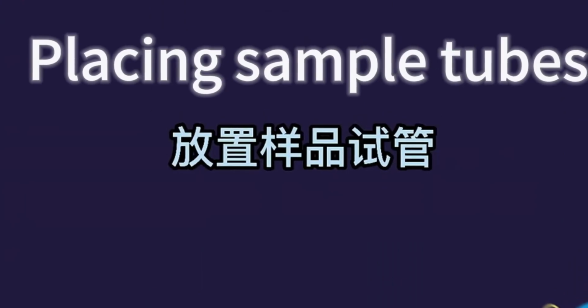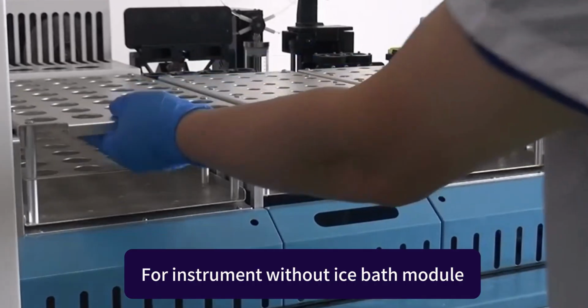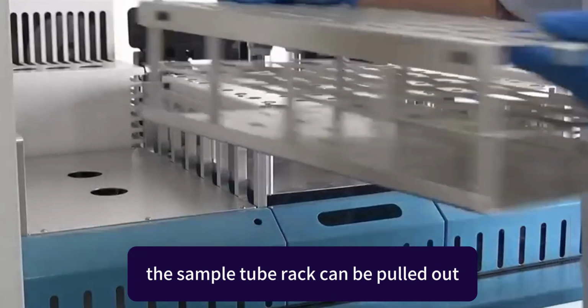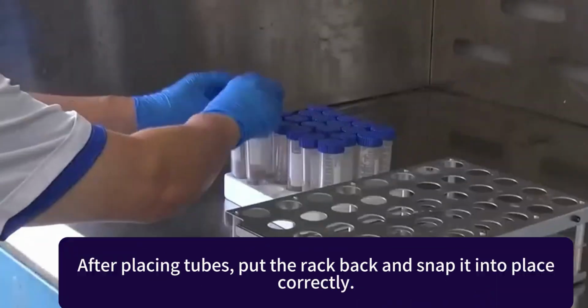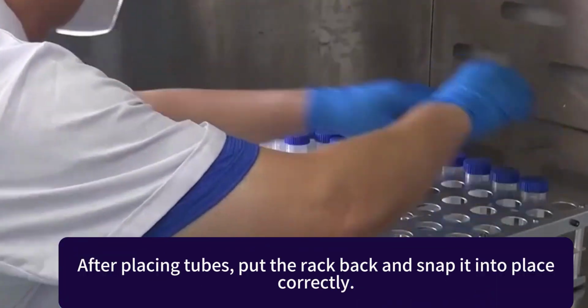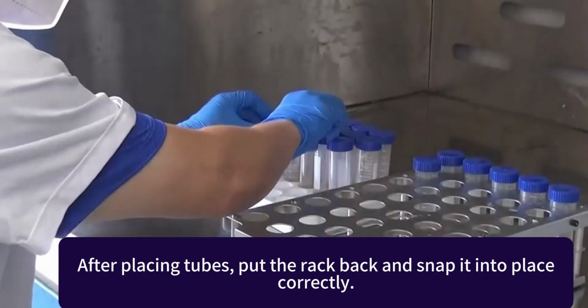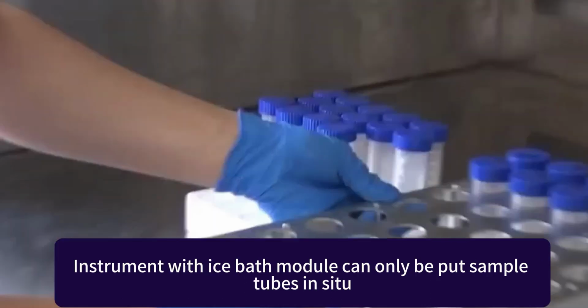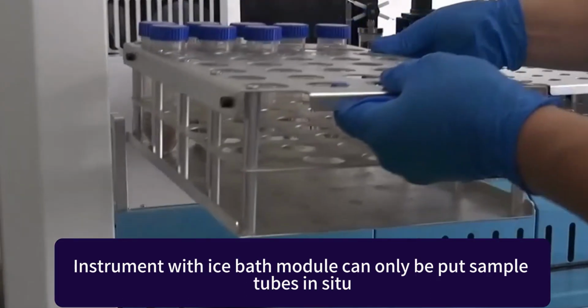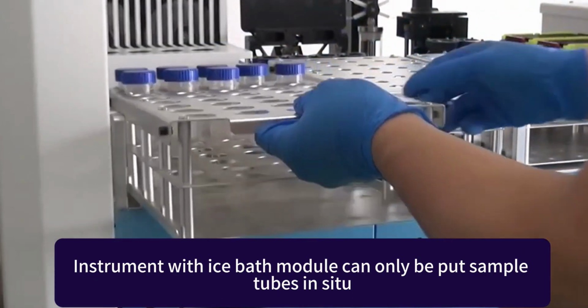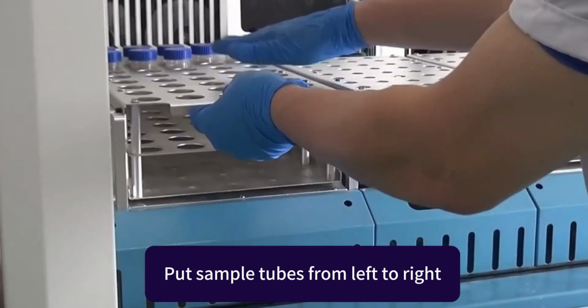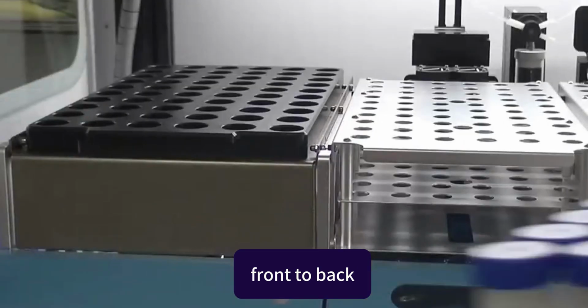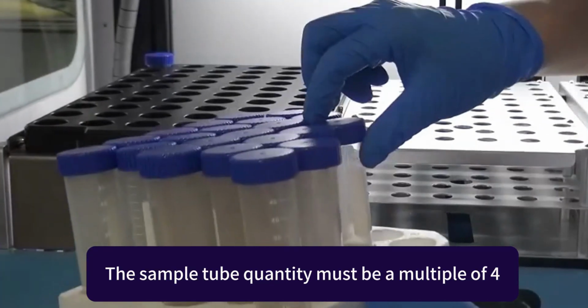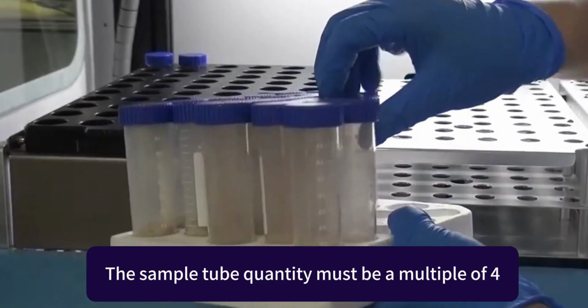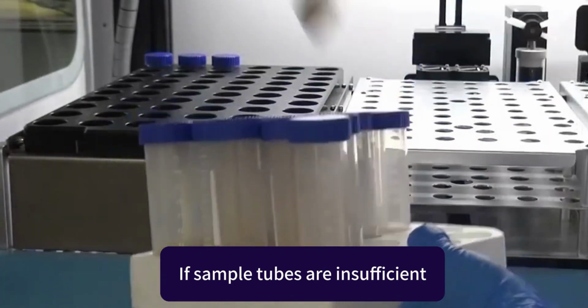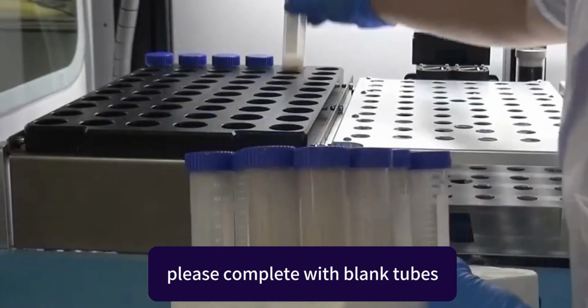Placing sample tubes. For instrument without ice bath module, the sample tube rack can be pulled out. After placing tubes, put the rack back and snap it into place correctly. Instrument with ice bath module can only be put sample tubes in situ. Put sample tubes from left to right, front to back. The sample tube quantity must be a multiple of 4. If sample tubes are insufficient, please complete with blank tubes.